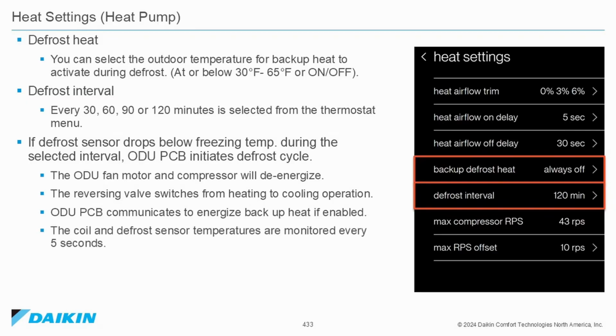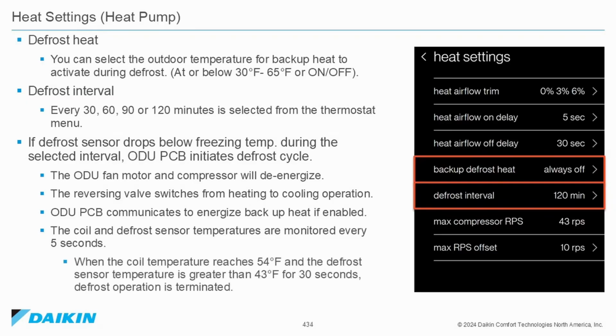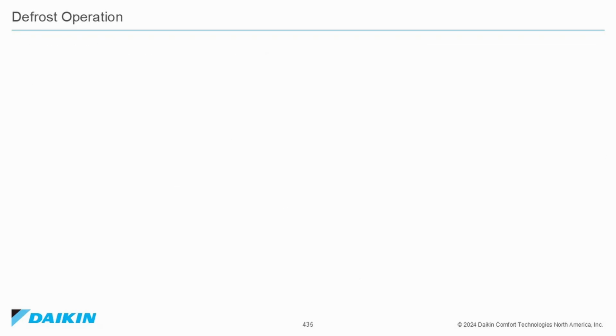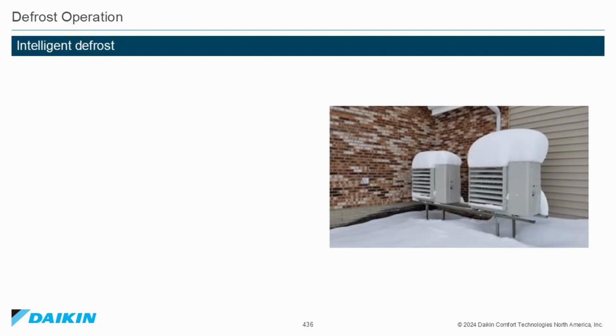The coil and defrost sensor temperatures are monitored every 5 seconds. When the coil temperature reaches 54 degrees Fahrenheit and the defrost sensor temperature is greater than 43 degrees Fahrenheit for 30 seconds, defrost operation is terminated. Defrost operation. Intelligent defrost.